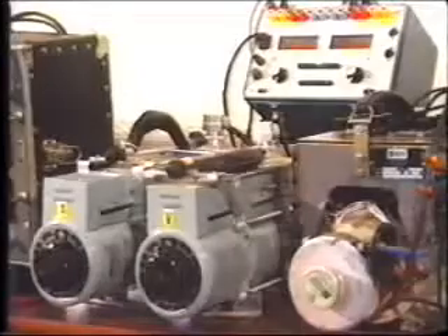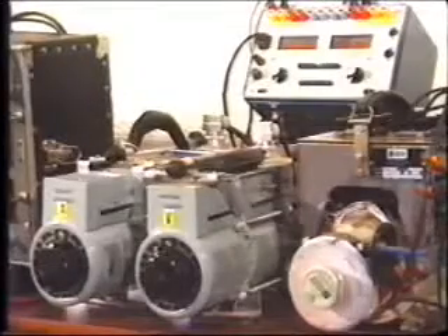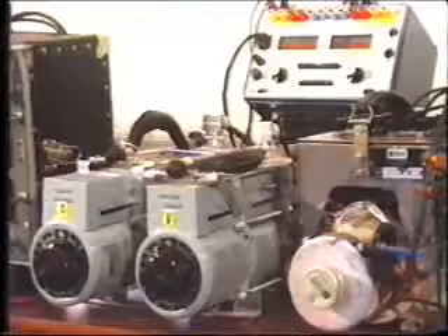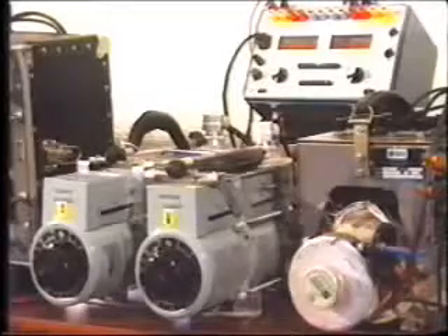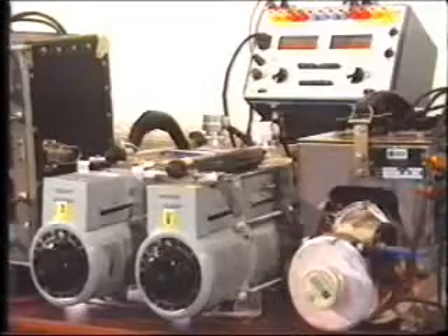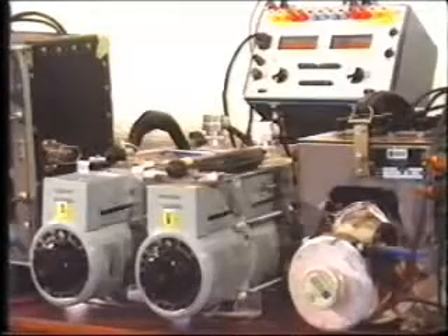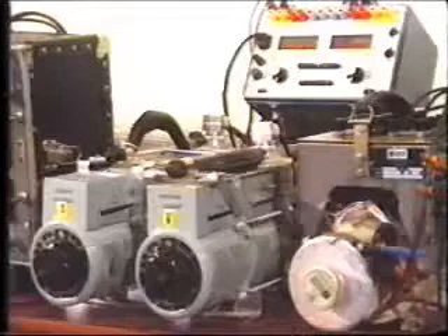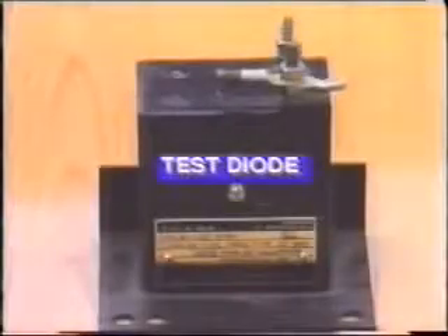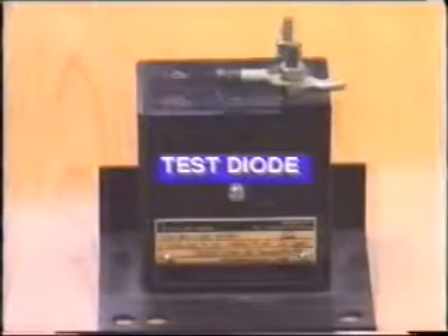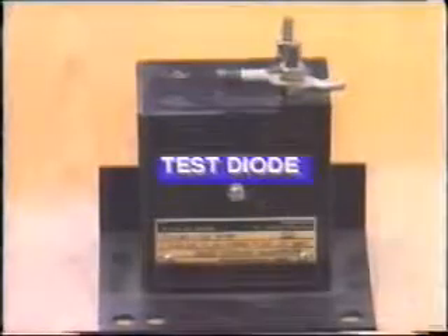You can see that a comprehensive test setup can be quite complicated and cumbersome. It may take far greater time to set up and check the test equipment than to perform the actual test. Moreover, additional special purpose test equipment is often required. For example, a test diode to produce harmonics for testing the harmonic restraint unit of a transformer differential relay.